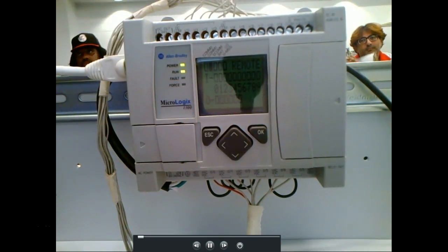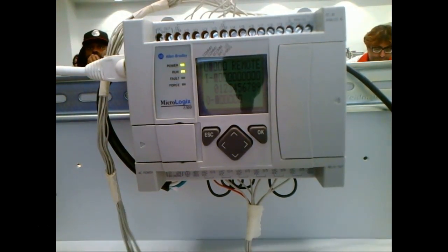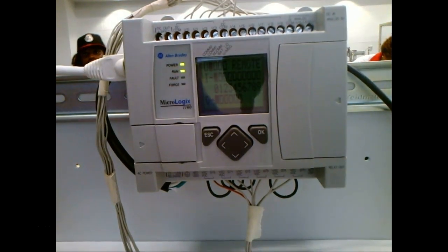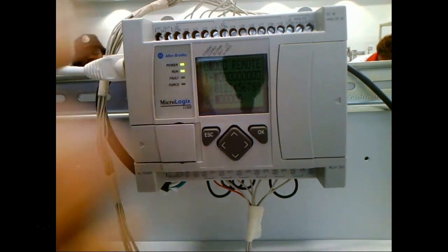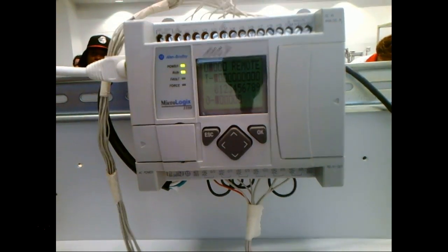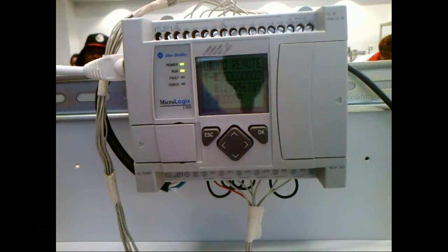So what I'm doing is I'm coming over here, and when I close that, my PLC sees that that input switch is turned on. So it's getting 24 volts DC into port 0. And if I looked at the input table, that input table would have just gone to 1 for that reason. Everybody okay? So these are true inputs.